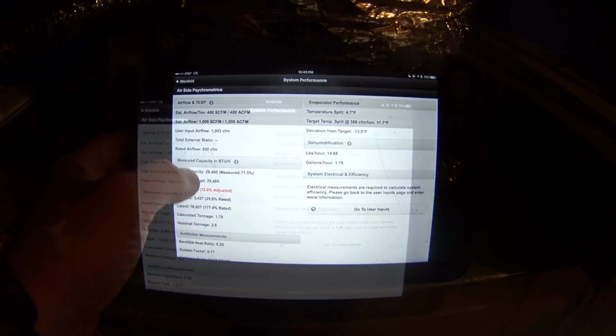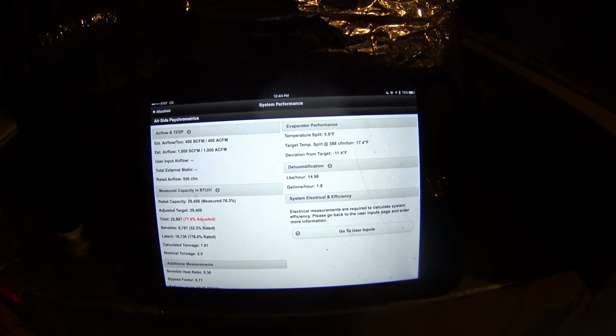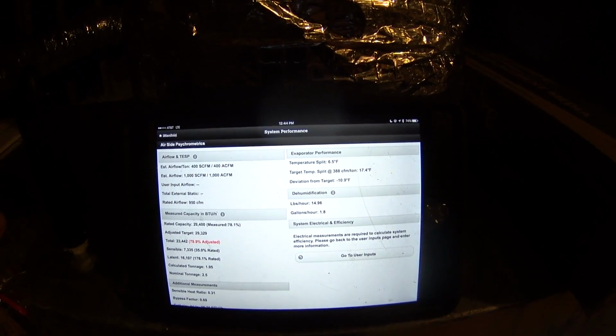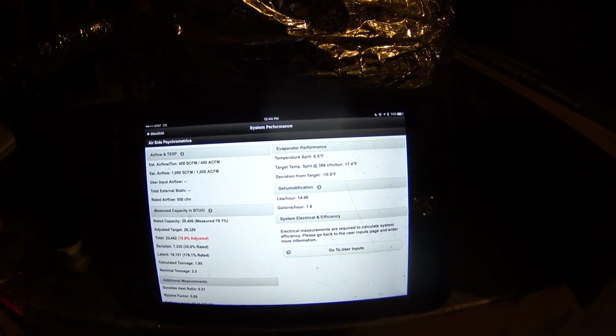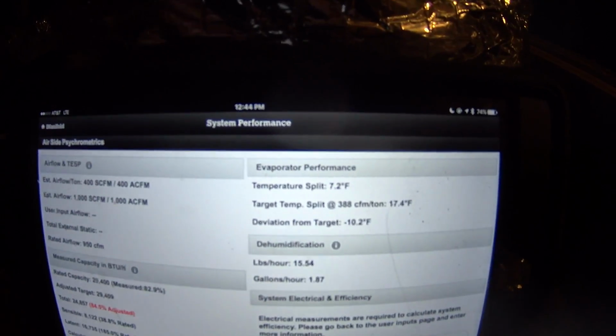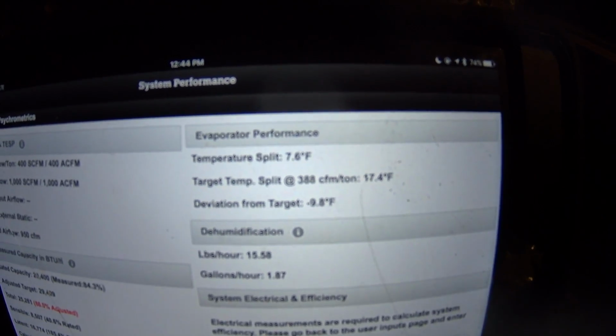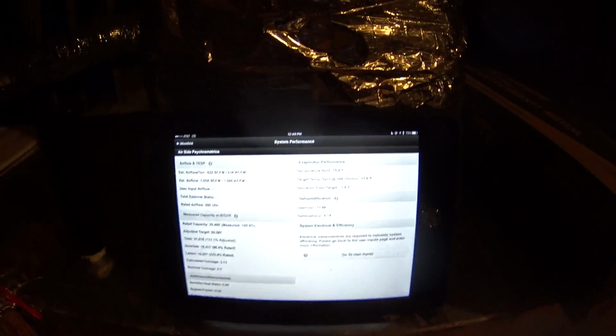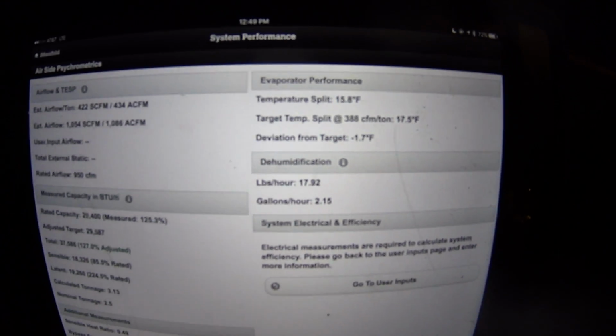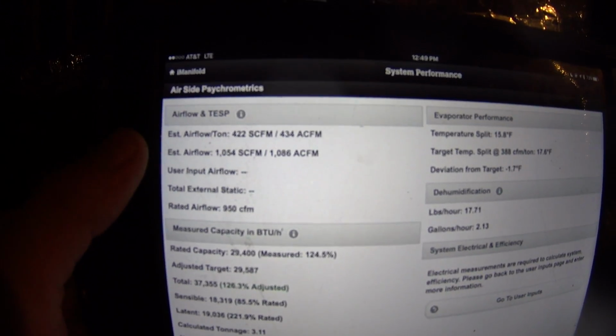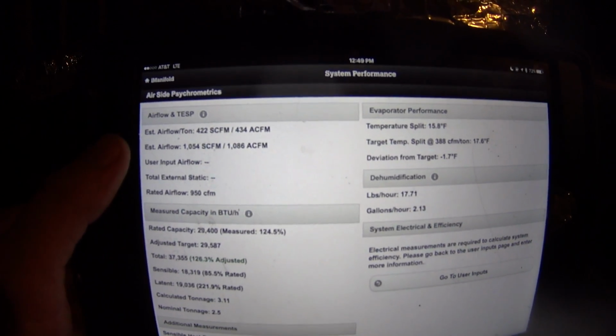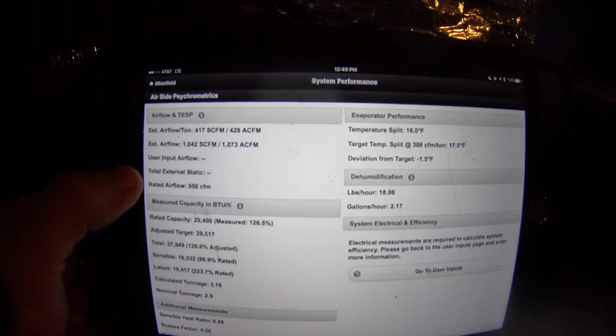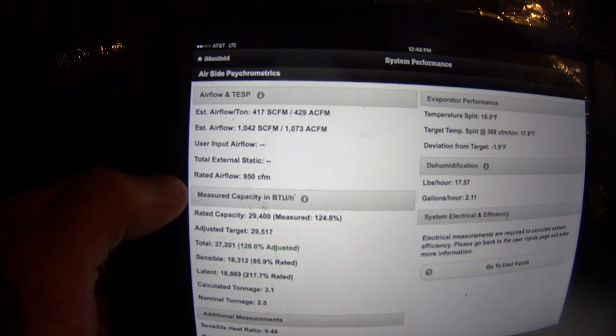and let's see what our system performance looks like. And our temperatures have not balanced yet. Right now we're showing a temperature split of 6.5. So we're gonna let it balance out for a little while. 7.2. We'll be back in just a minute. So we've balanced out pretty well, and we are about 1.7 degrees off of target. Calculated airflow is coming out just over 400 per ton and 1,000 CFM. The AHRI match is rated at 950 airflow.